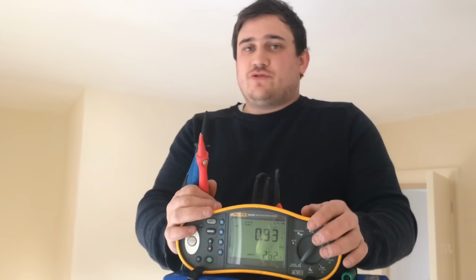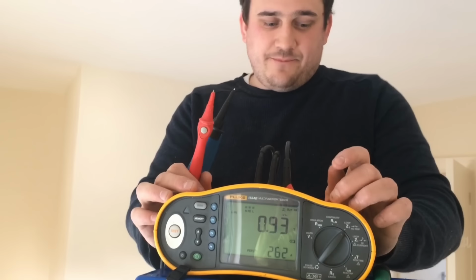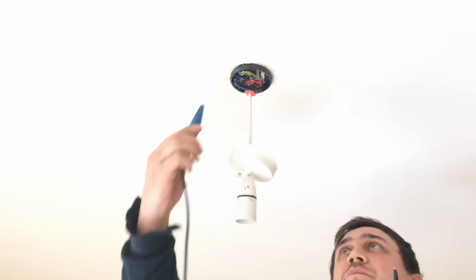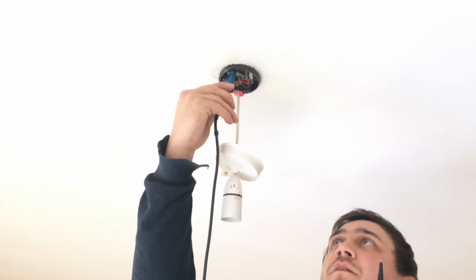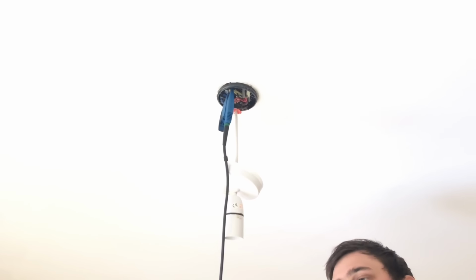We're now performing our earth fault loop impedance test, otherwise known as a ZS test. In this instance we're using a 3-lead no trip test because we have RCDs in the circuit. We do know we can calculate this measurement by doing our ZE plus our R1 and R2. However, at college we have been taught as long as we take the necessary precautions, i.e. GS38 probes, then measurements are always the best way forward. First of all, I'm going to probe onto my earth terminal.